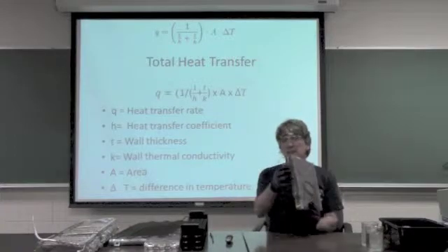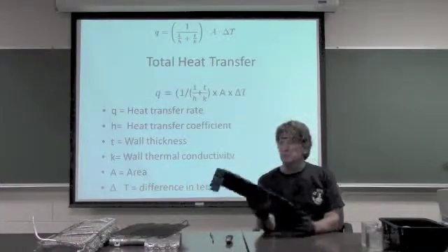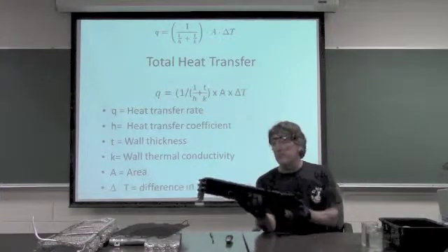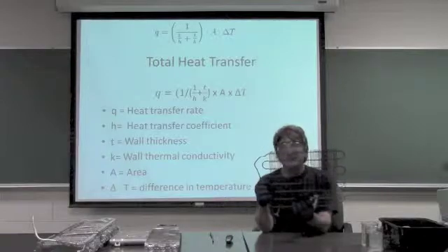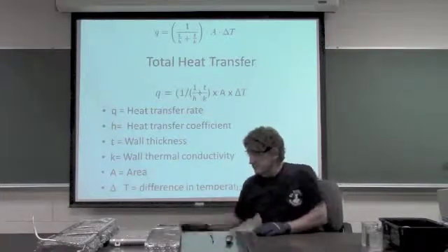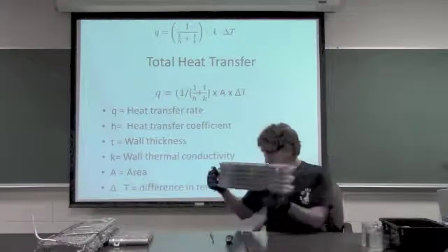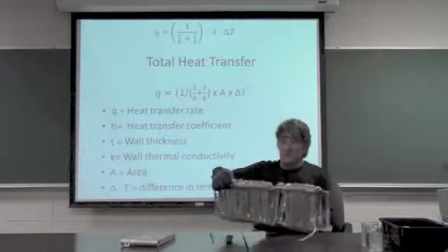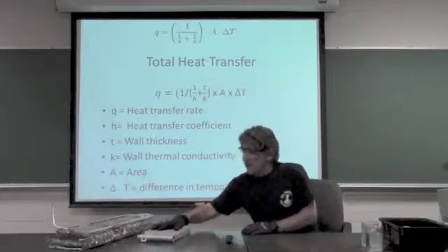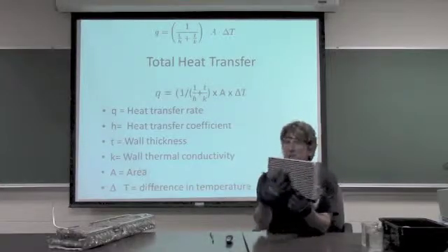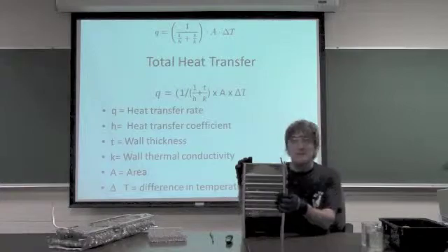I have aluminum fins and copper tubes. I can have copper tubes and aluminum fins painted for a different color that allows me to transfer heat quicker, so color does matter. I can have steel with very few fins. I can have aluminum, all aluminum fins, all aluminum coil. I can have aluminum fins with all this prickly stuff on it, gives it more surface area. I can have microchannel coils, which has a lot of physical area, but they're physically small and light. I can have bigger coils with copper fins and aluminum, depending on my application.